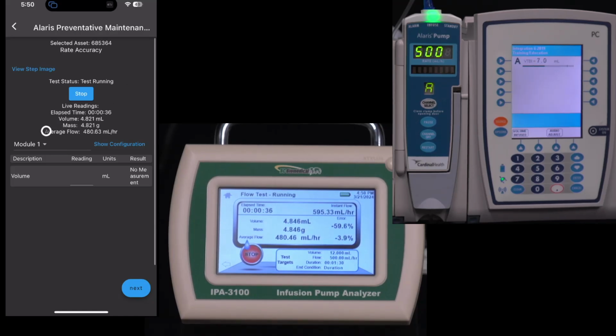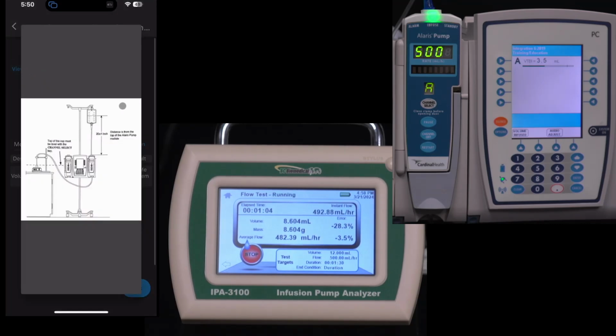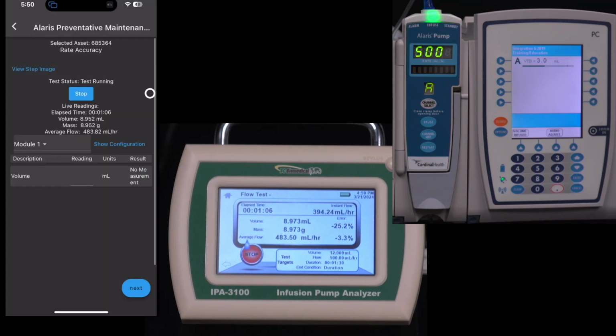Now we also have a setting here for Module 1. MyBC Mobile is also set up for using with the IPA 3400, which is a 4-channel infusion pump analyzer, but the 3100 is a single channel, so we only have access to Module 1. We also have a setup picture available for this test, which we can view. It shows us the configuration if we need to see that, and that is entered at the time that we create the auto sequence.